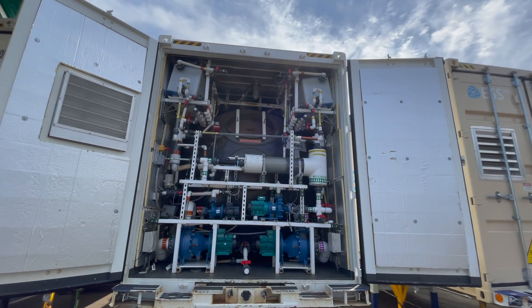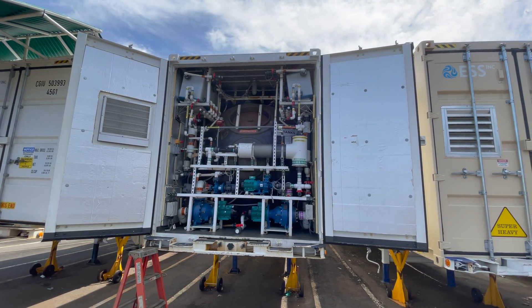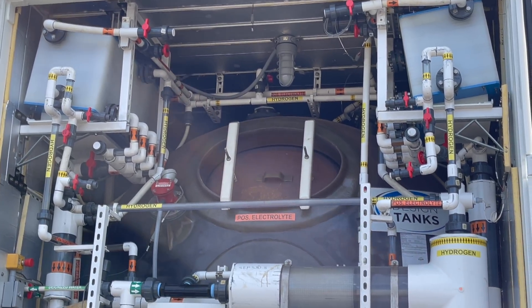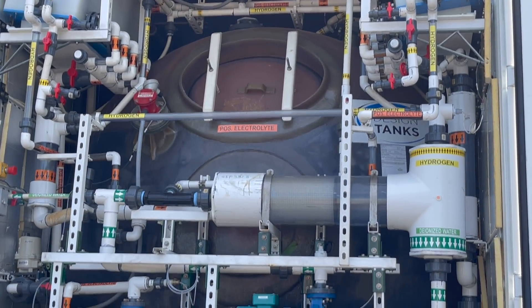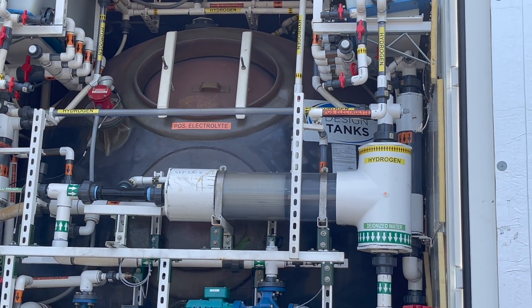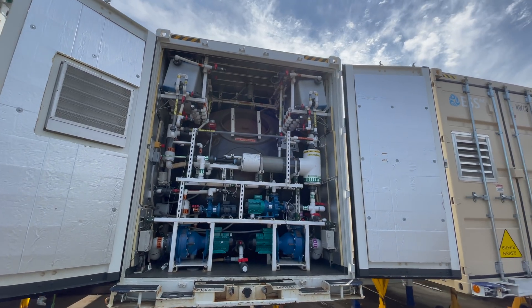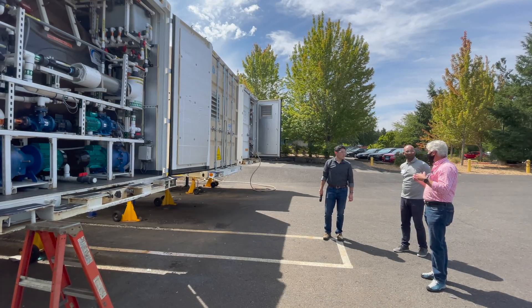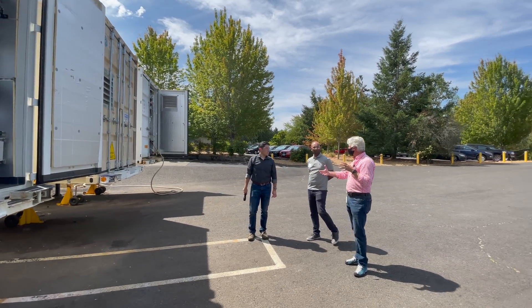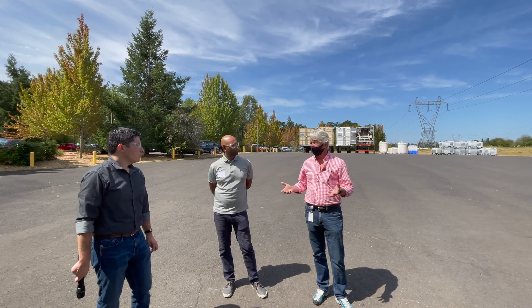This is all the mechanical equipment in the energy warehouse. What you're seeing down below is the main pumps to run the equipment. Above that is the electrolyte health system — all of that equipment is for cycling the electrolyte to maintain it and balance its chemistry. That's something unique to flow batteries: we can run that continuously even while operating the battery and keep the electrolyte in balance and clean. Every battery off-gasses or has some side reaction during every charge cycle. In our closed loop system, we created technology to process that continuously so the electrolyte is continuously refreshed.